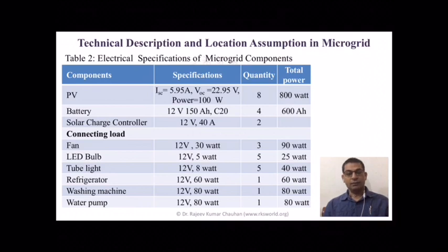The C20, what does it mean? Why is it C20 and how does it affect things? C20 means the battery capacity is 150 Ah, so this battery can supply a maximum of 7.5 amperes, meaning 150 divided by 20 equals 7.5. So we can charge the battery at 7.5 amperes or discharge it at 7.5 amperes - this is the rated current during charging and discharging.